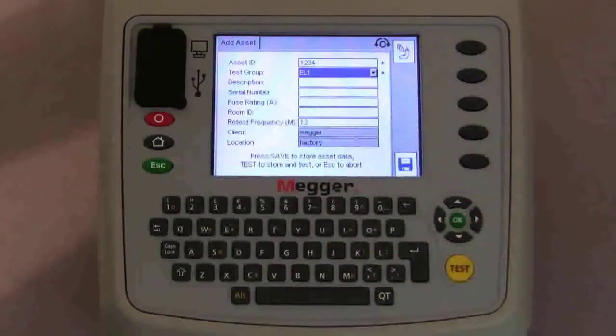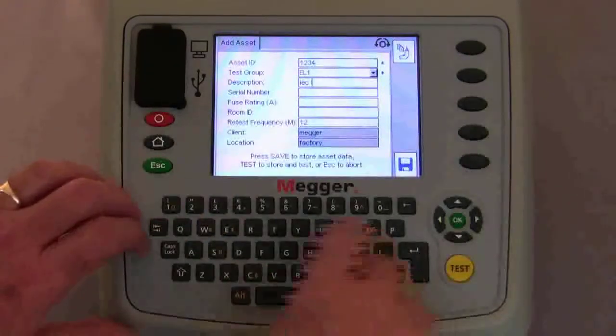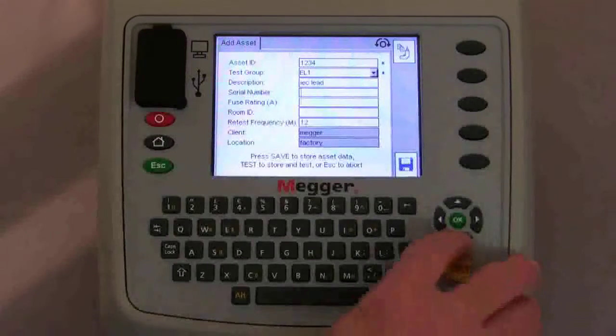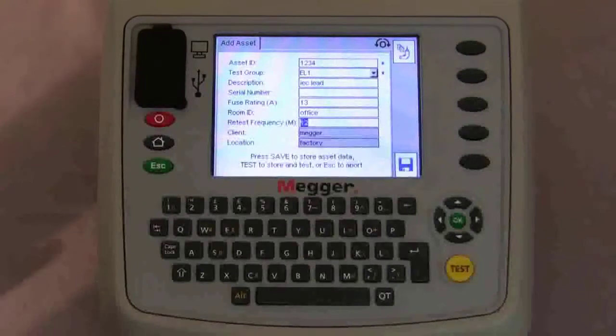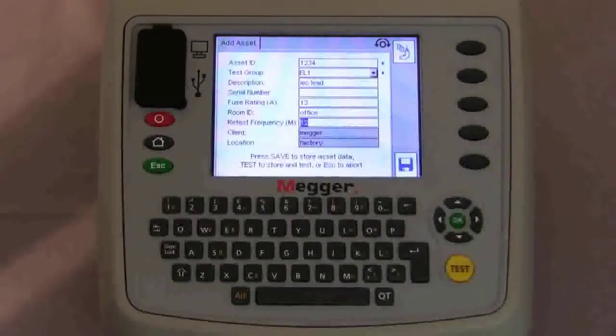Using the navigation keys we move down and type in the description, serial number if applicable, the fuse rating, and the room that the piece of equipment is in. Moving down we have the retest frequency on the asset, and we can see we're in the client and location of Megger and the factory. At this point you can press the hot key to save the asset to memory, or press the test button to save and commence testing. If you have duplicate pieces of equipment you can press the hot key to bring the information back up on the next asset and just change the asset identification and any descriptions.